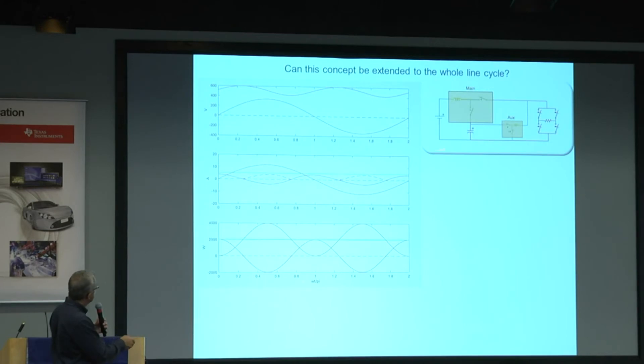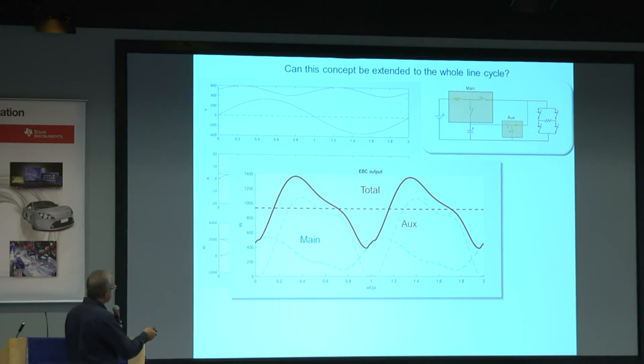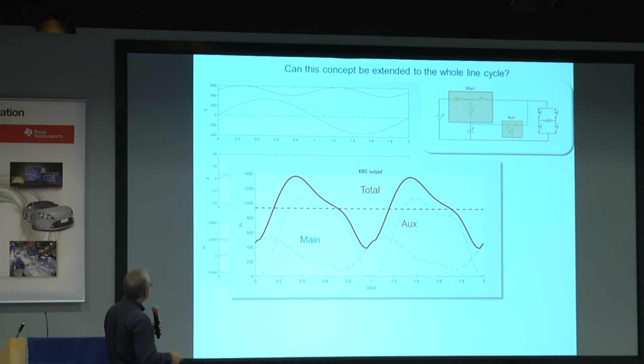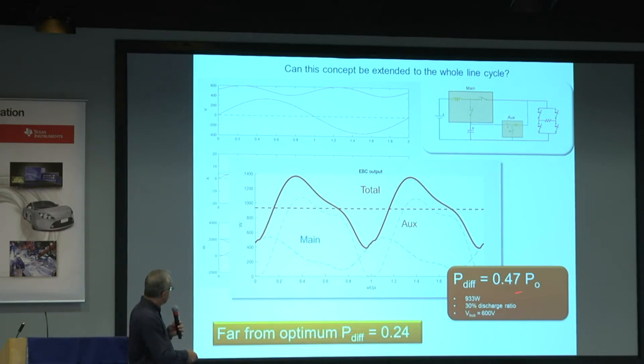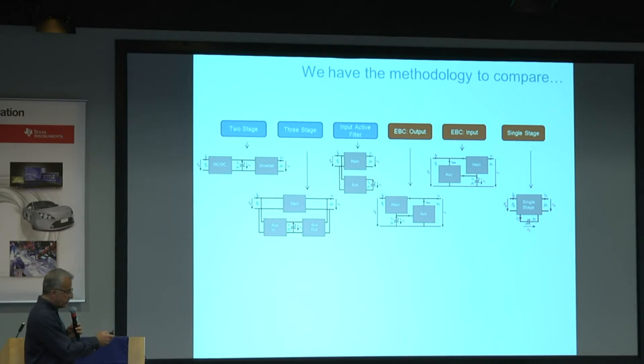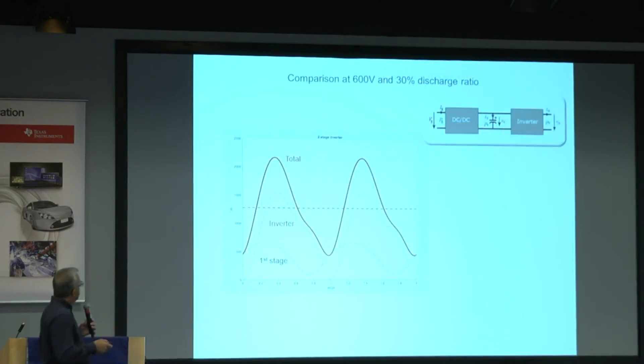We plotted the external waveforms and then plotted the power processed by each component — not the nominal output power but the differential power processed by the components. We got values for the main converter, the auxiliary converter, and the total was 0.47, meaning we were processing around 900 W. Was it good or bad? It was, in any case, far from the minimum possible. So we proposed another architecture similar to that one and compared it with typical approaches: two-stage, filter, three-stage. We also tried a single-stage converter, made the comparison, and this is what we got.